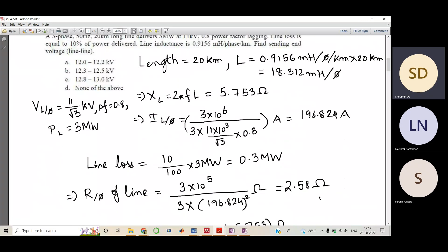So the current flowing through the transmission line is the load divided by the voltage and the power factor. It comes out to be 196.824. Then the line loss, they have said, is 10% of this 3 megawatt power being delivered. When you do it, it comes out to be 0.3 megawatt. So the per phase resistance of the line is this power divided by 3 times I squared. We multiply by 3 because this is the per phase current, and it's actually 3 I squared R. So you calculate, it comes out to be 2.58 ohms. So your Z per phase would be 2.58 plus j 5.73.